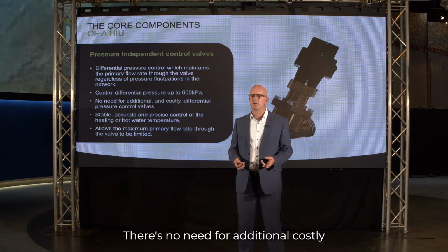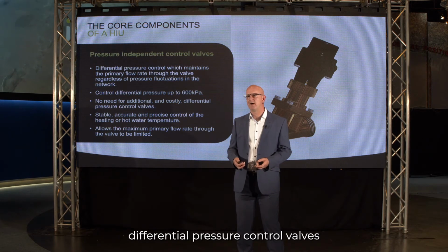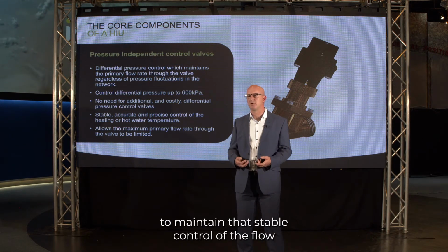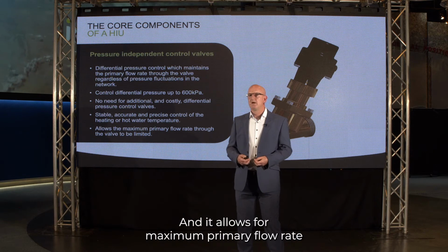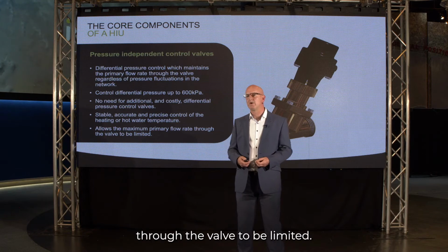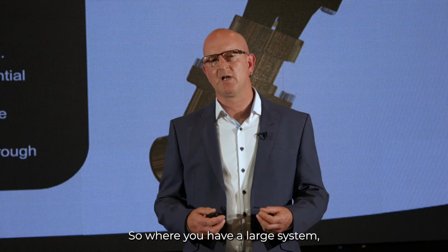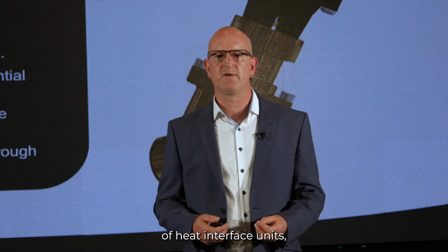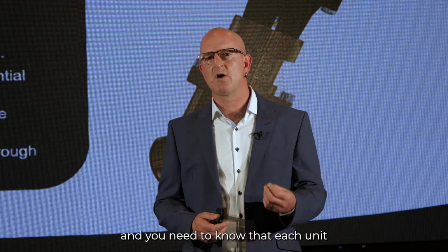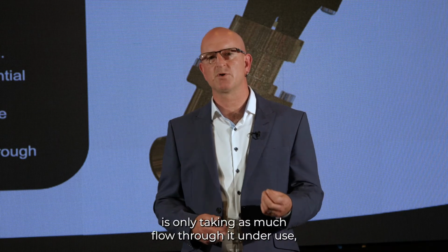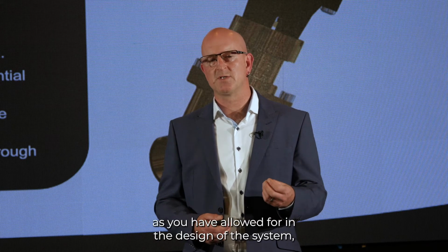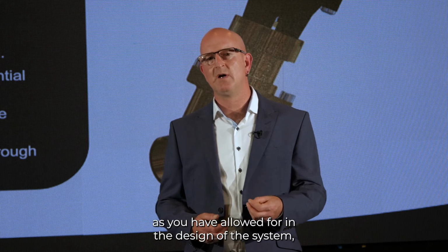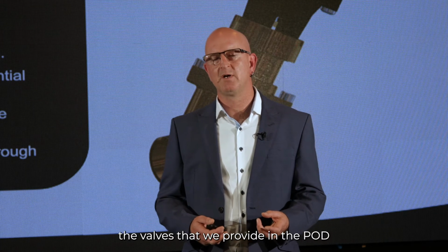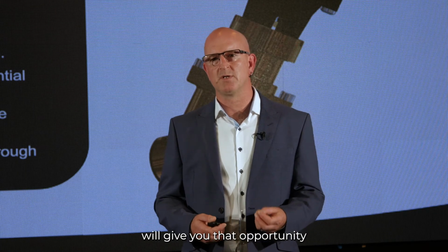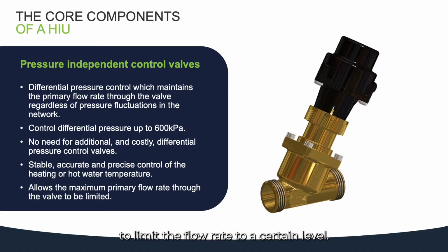There's no need for additional costly differential pressure control valves to maintain that stable control of the flow through the appliance. And it allows the maximal primary flow rate through the valve to be limited. So where you have a large system, with potentially hundreds of heat interface units, you need to know that each unit is only taking as much flow through it under use as you have allowed for in the design of a system. The valves that we provide in the pod will give you that opportunity to limit the flow rate to a certain level.